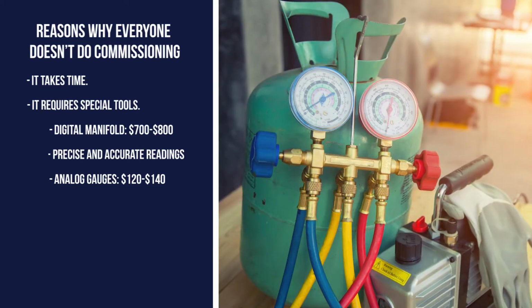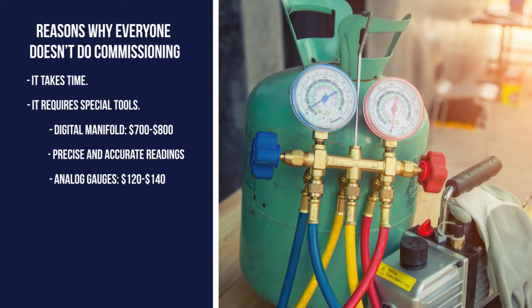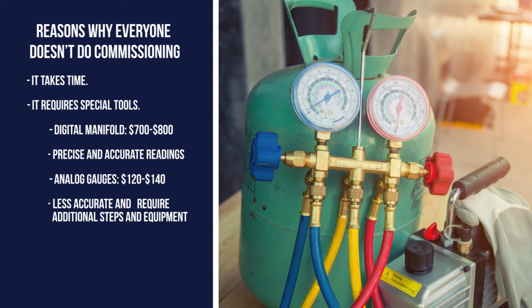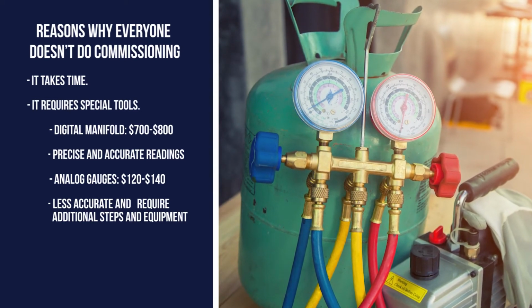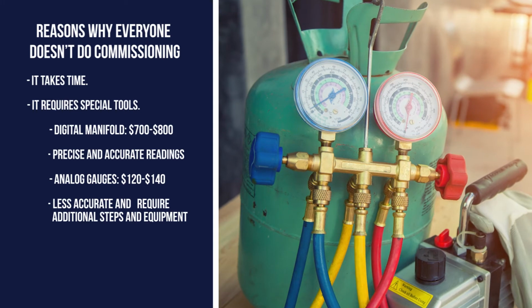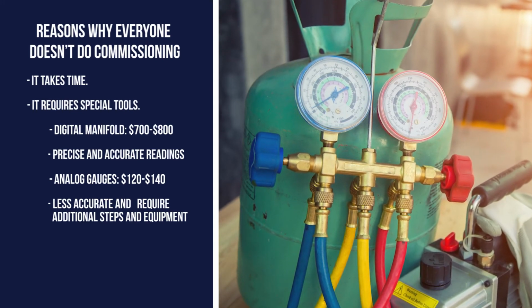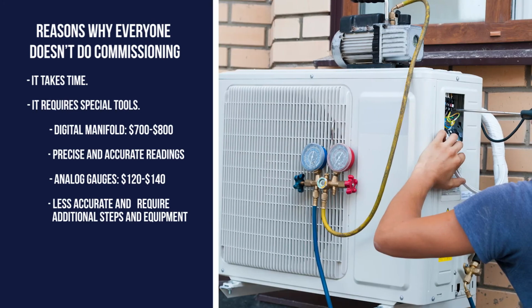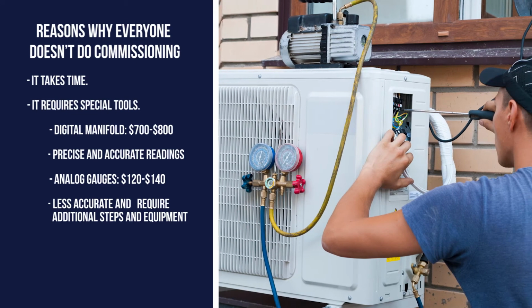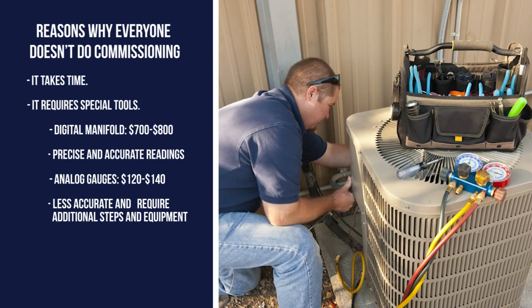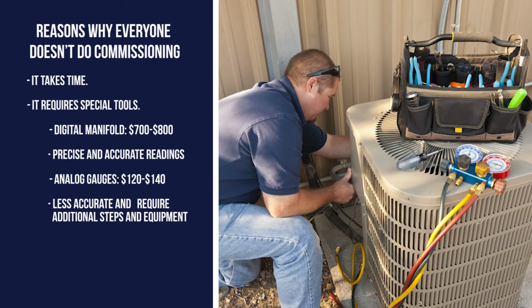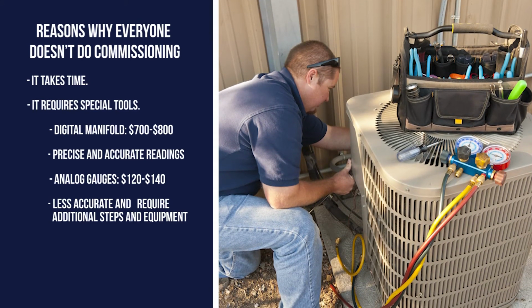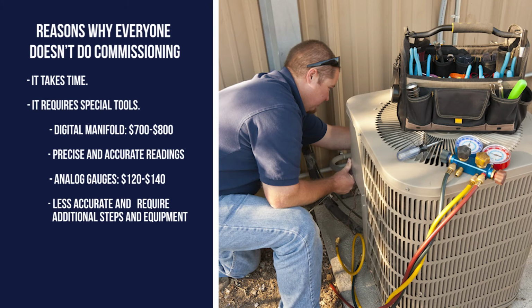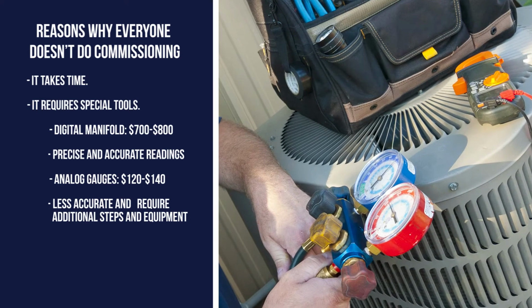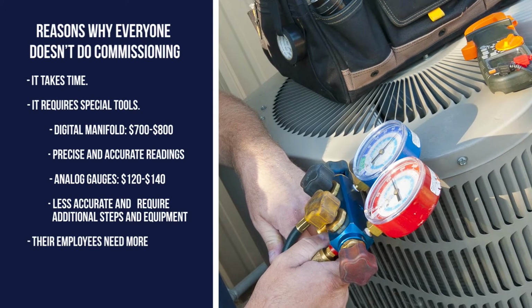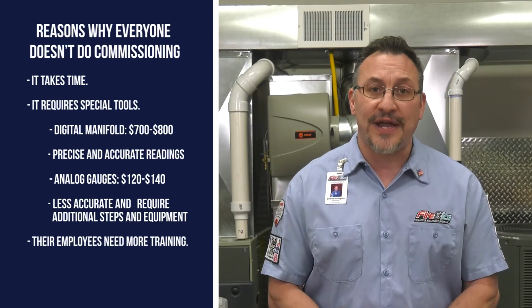The old school analog sets are inexpensive, costing about $120 to $140. They're less accurate than our digital manifold and require extra steps and equipment that the technician may or may not have with them - all of which is included in the digital manifold set. So by using the older analog set, if you don't have the right training and the extra equipment, like pressure-temperature charts that are required, you're doing a disservice to the system because you cannot properly commission it without this information.